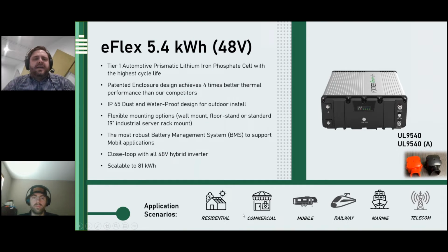With the E-Flex, it's a 5 kW output, and so we, under warranty, allow 2 E-Flexes with 1 Sol-Ark 12K inverter that has the 9 kW battery inverter capacity. If you have 9 kW battery inverter capacity and 10 kW of battery output with its 5 kW output rating, that means it's more than adequate to supply the full power output rating of the Sol-Ark with just 5.4 kilowatt hours times 2, almost 11 kilowatt hours worth of battery capacity.